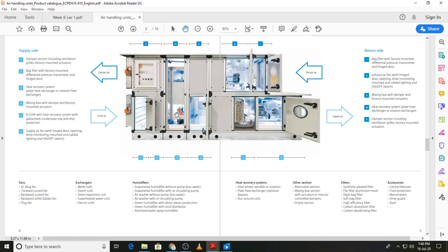After the fresh air filter, the air goes into an energy recovery unit or heat recovery unit — this is optional and may not be present in all AHUs depending on the client's requirement. The air from outside mixes with the recirculated air in the mixing box, then passes through the coils — you can have a heating coil or a cooling coil, or more than one coil depending on requirements. If it is a cooling coil the air is cooled, and the supply fan then sends it to the conditioned space.